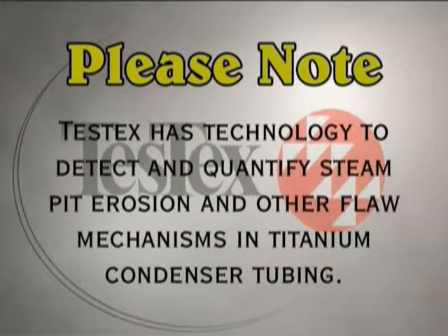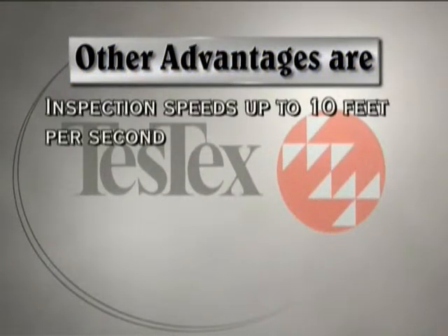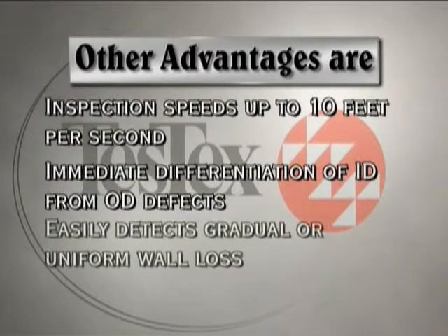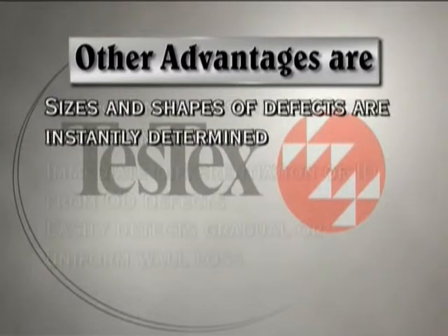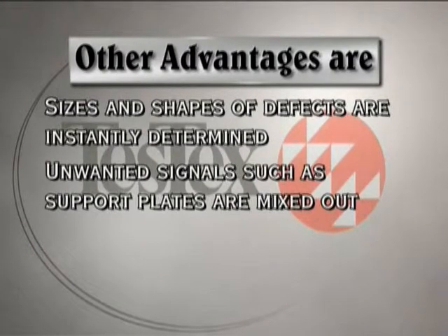TesTex has the technology to detect and quantify steam pit erosion and other flaw mechanisms in titanium condenser tubing. Other advantages include inspection speeds up to 10 feet per second, immediate differentiation of ID from OD defects, and the ability to easily detect gradual or uniform wall loss. Sizes and shapes of defects are instantly determined, and unwanted signals such as support plates are mixed out.